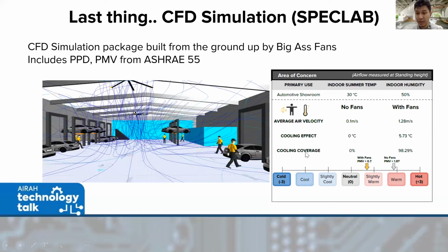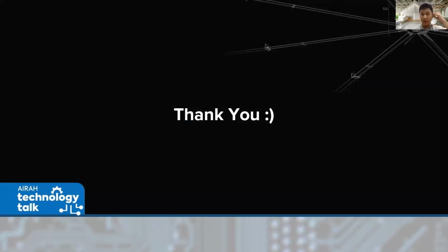And as you can see with the PMV, without the fans their PMV was 1.87. With the fans in, it's 0.7. This one certainly does not meet the ASHRAE 55 standard, because it needs to be less than 0.5. But for unconditioned spaces, with fans we can at least improve the thermal conditions, and that's the goal. Thank you. That is all.